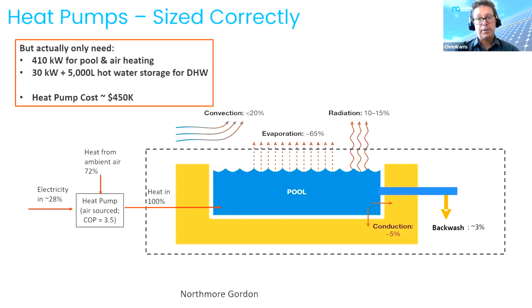But when you look at the data for this facility, they actually only need 410 kilowatts for pool and air heating. That's actually the maximum heat consumption that it uses. And on the domestic hot water side, they've got enough capacity there to provide hot water for the 14 showers running continuously 24 hours a day. Now, they obviously don't use that much hot water.